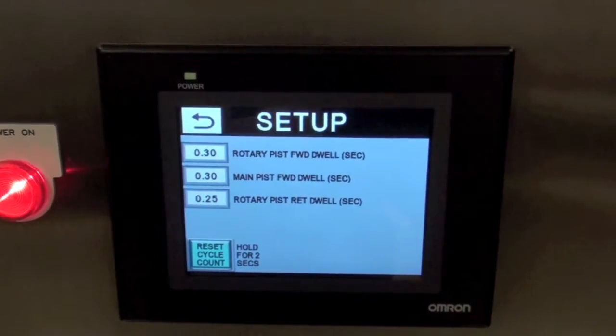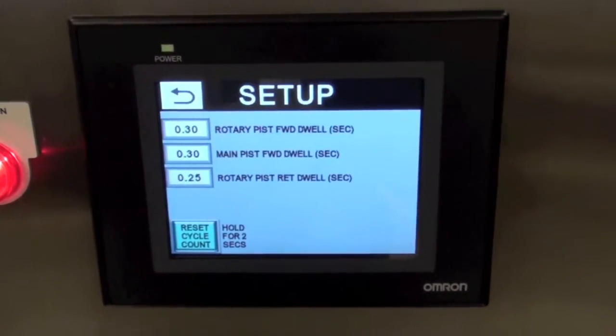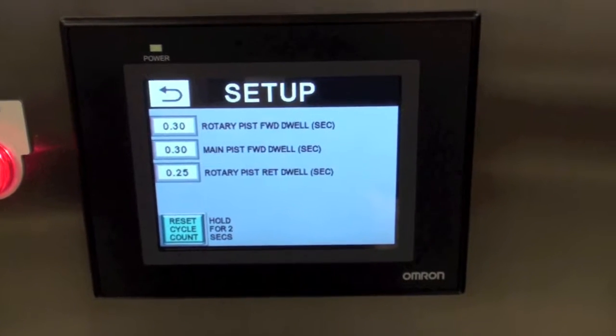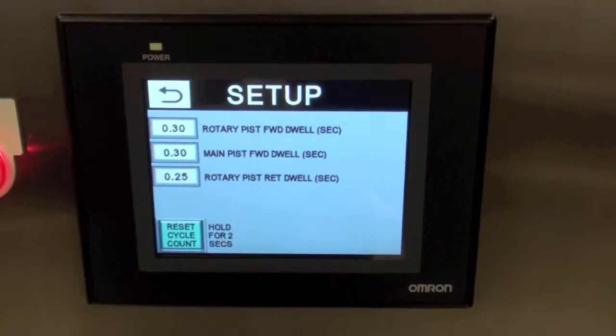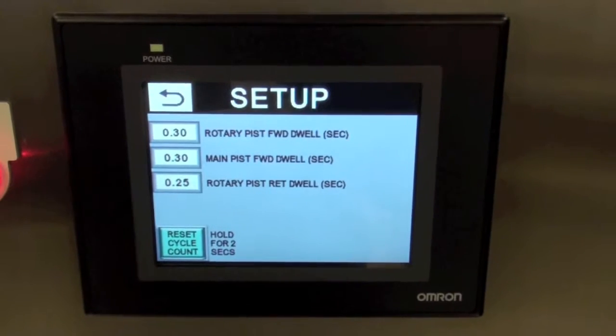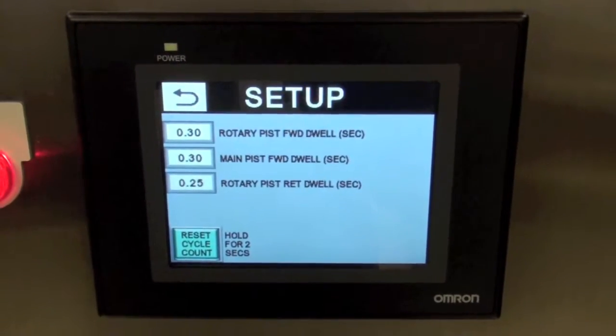Your next setting is the main piston forward dwell, which is also set to 0.3 seconds. What this monitors is the time the piston stays forward after dosing before the valve closes.